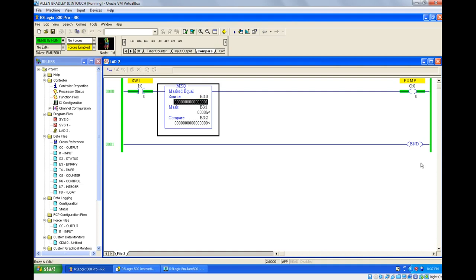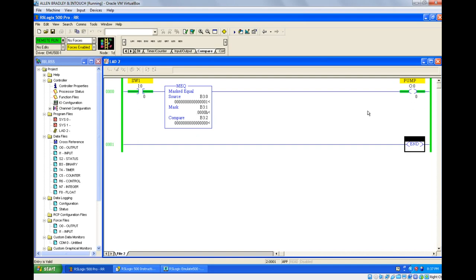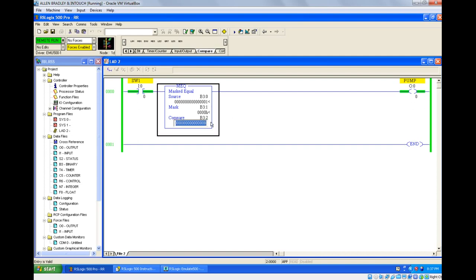Let us change this to 1. Now both the values are not equal, but still your pump is on. So what does masked equal mean? If you are not activating your mask bit, whatever value you give in the source and whatever value you give in compare, both will appear equal — meaning the pump is on. Why is the pump on? Because the masked equal instruction is giving output.